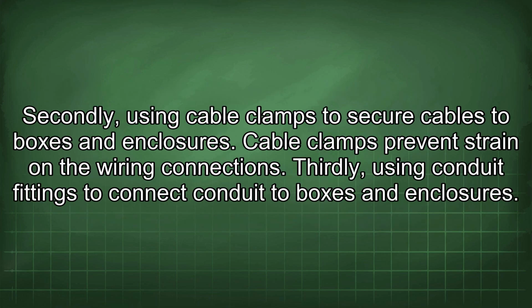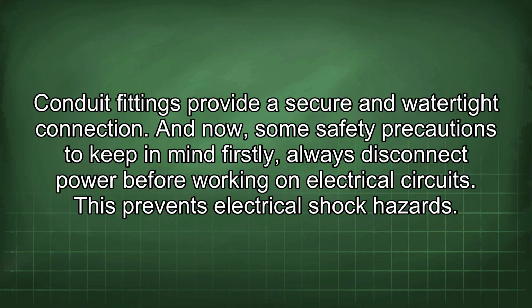Secondly, using cable clamps to secure cables to boxes and enclosures. Cable clamps prevent strain on the wiring connections. Thirdly, using conduit fittings to connect conduit to boxes and enclosures. Conduit fittings provide a secure and watertight connection. And now, some safety precautions to keep in mind.